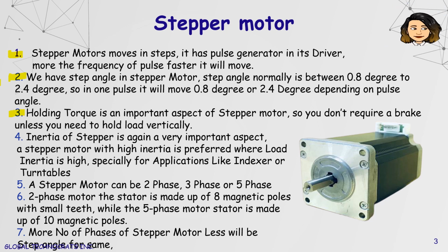Holding torque is an important aspect of a stepper motor. So you don't require a brake unless you need to hold a load vertically. Inertia of a stepper is again a very important aspect. A stepper motor with high inertia is preferred where load inertia is high, especially for applications like indexers or turntables.